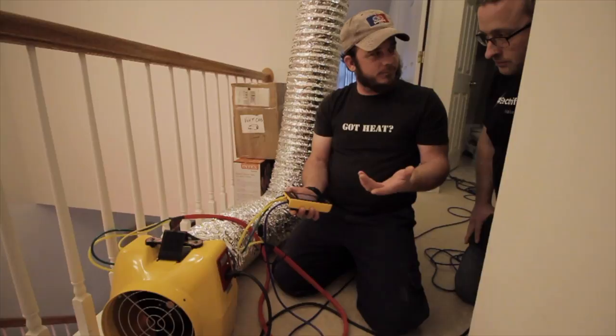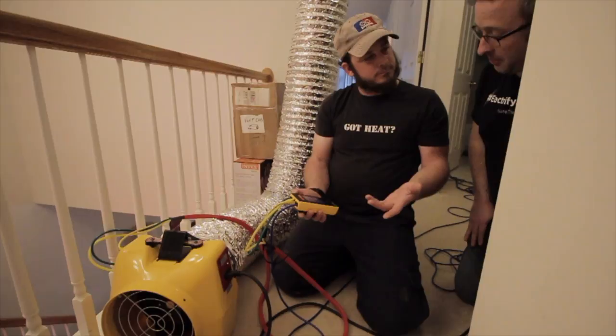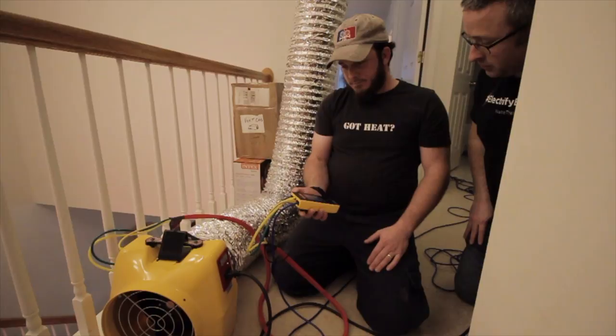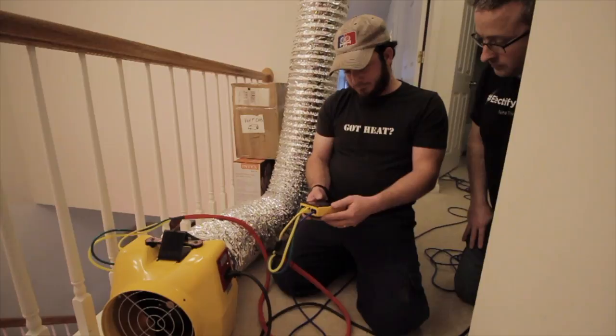So open was about what we have. Yeah, it looks like it's probably going to hit 100% fan speed before it zeroes it. So technically you need a ring in between, but the number you got before probably wasn't that far off. Right. If it could get there, which I don't know if it's going to, you're still going to get in the 190, 200 range, something like that. We're going to open it back up again and give it another chance, because I feel like we're going to max out the fan's capacity before we reach 2 Pascal. Interesting. Very interesting.